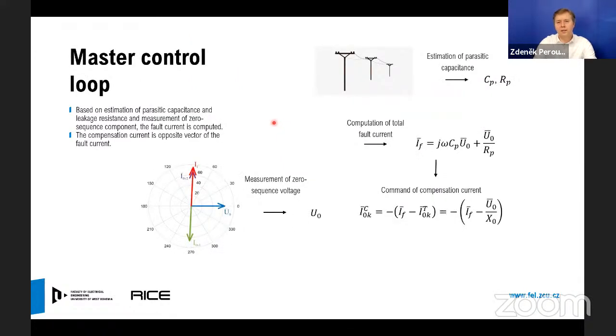How is the compensation current generated? We do the online estimation of the parasitic capacitance and parasitic resistance of the grid, as I explained, using the pseudo-Dirac impulse. And we measure the zero sequence voltage. With these known parameters, we are able to calculate the fault current, having the reactive part and the active part. The fault current is partially compensated by the transformer. This current can be calculated from the zero sequence impedance of the transformer and the known zero sequence voltage. And the remaining part of the compensation current, that is, when we subtract the compensation current generated by the transformer from the total fault current, we get the command for the generation of the compensation current by our converter.